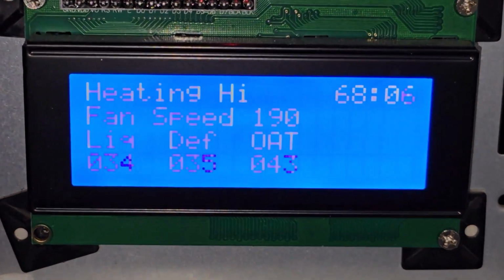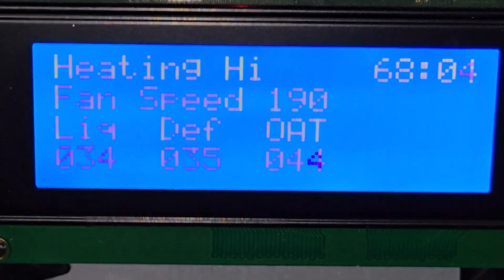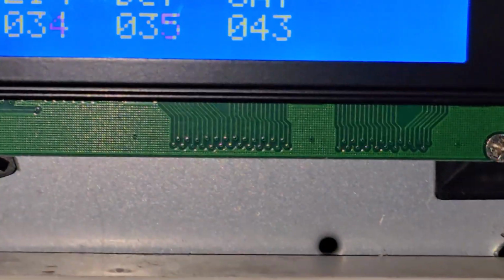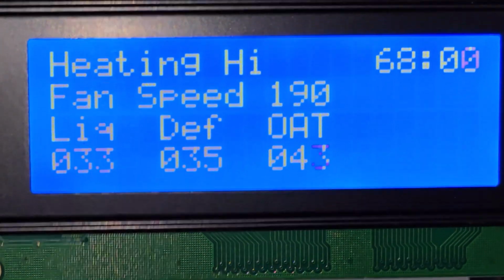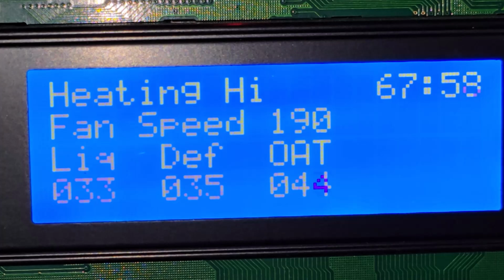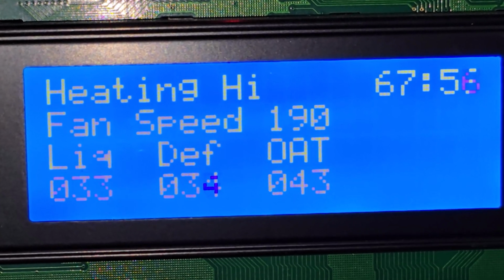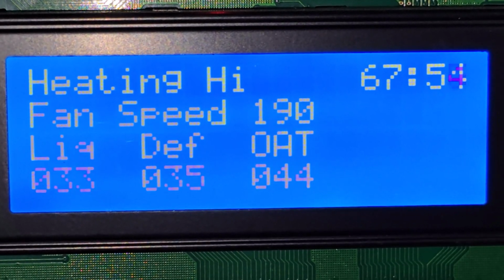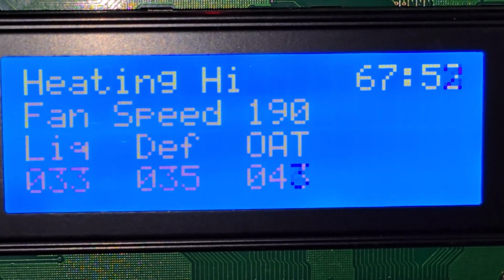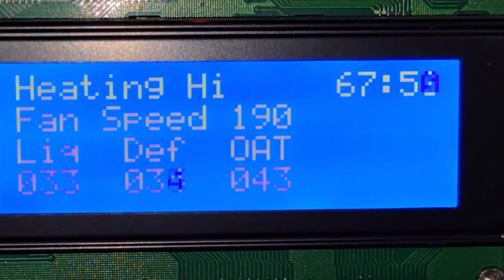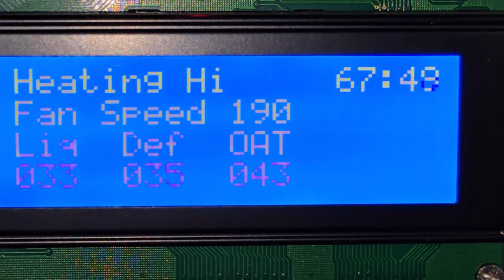You see that display is working fine, man. There's like no scrambling, no weirdness on that. We're on high heat. Defrost timer is at 67 minutes. It rolls over every 90 minutes and checks the thermistor, which is at 34 degrees.